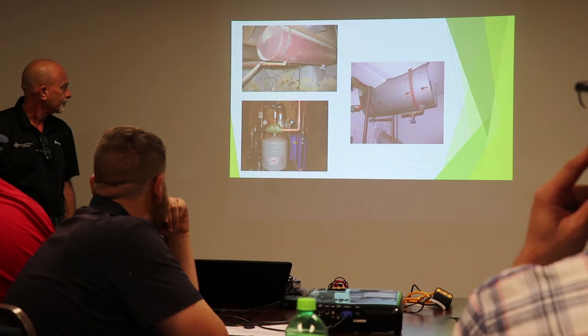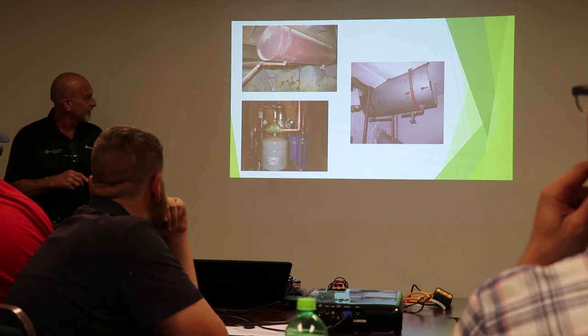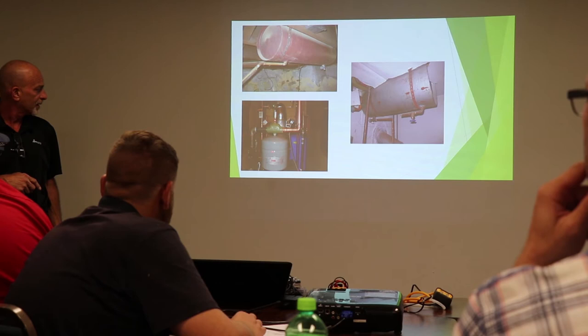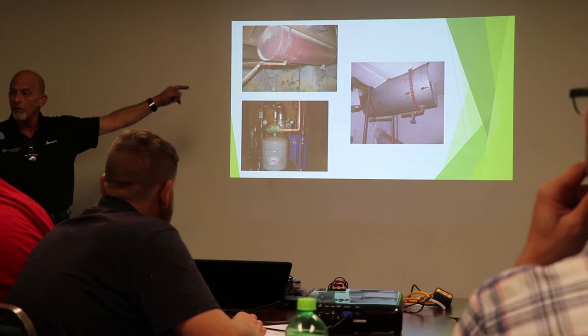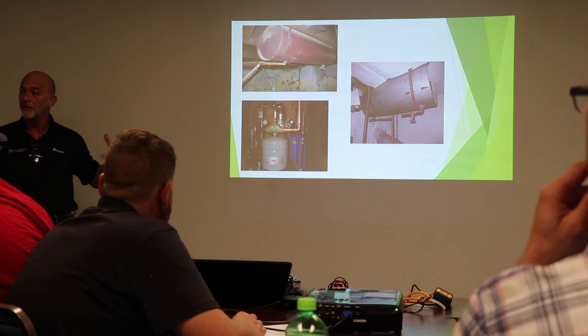Check our expansion tanks. You'll still see expansion tanks like this up in the ceiling. They're still out there, big steel tanks. A modern tank is usually mounted on an air scoop with an auto vent right on there. Any tank though, it's an expansion tank. Water gets hot, it's going to expand. We need a place for it to expand. Whole purpose of the tank.